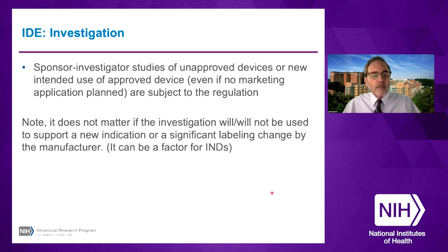Now, I do want to mention that in the regulation of devices, it doesn't matter if the investigation will or will not be used to support a new indication for use, or if it will or will not be used to support a significant labeling change by the manufacturer. I make this point only because those two things can be factors in the application of the investigational new drug regulations, but they have no bearing on the application of the investigational device exemption regulations.